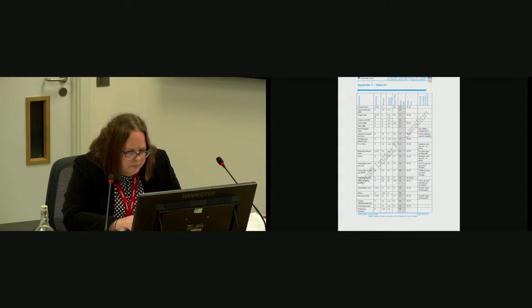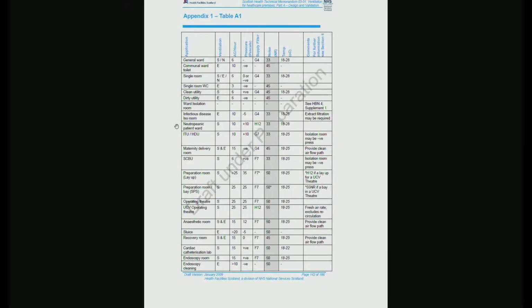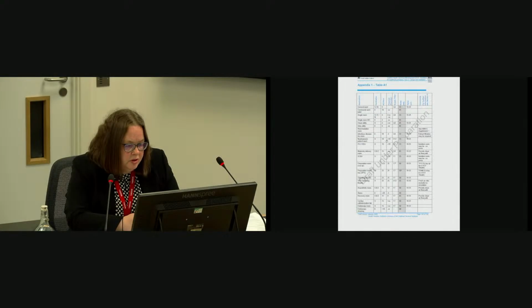Yeah. Now, let's go and look at the neutropenic patient ward entry, which is about 9 rows down. If we ignore for a moment what neutropenic patient ward means - we'll discuss what that means and what it might mean and what the uncertainty is in a moment - what's it telling us that this guidance is proposing for the ventilation for that space? So it's telling us 10 air changes per hour, positive pressure of 10 pascals, and HEPA filtration.